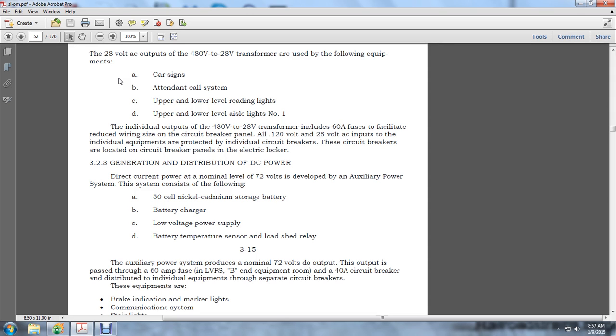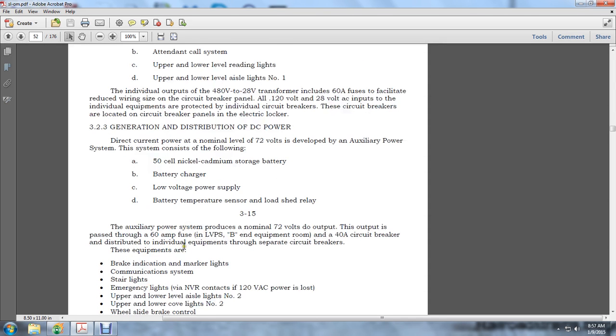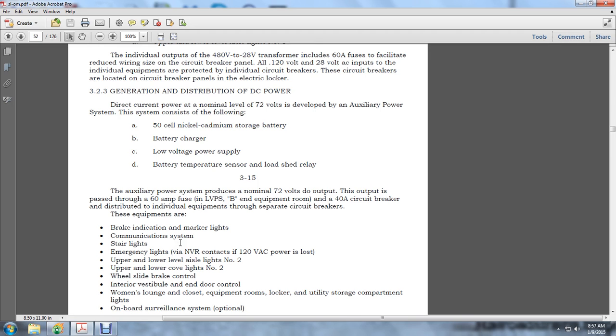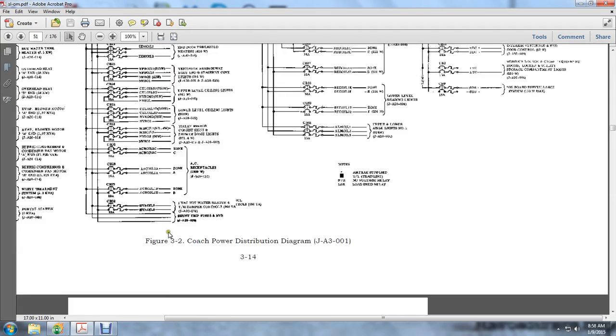3-2-3, the distribution of DC power. The direct current power, nominal 72 volts, is developed by an auxiliary power system. The system consists of the following: a 50 cell nickel cadmium storage battery, a battery charger, low voltage power supply, a battery temperature sensor, and a load shed relay. The auxiliary power system produces a nominal 72 volt DC output. The output is passed through a 60 amp fuse to the LVPS at the B end of the equipment room, and a 40A circuit breaker is distributed to individual equipment through separate circuit breakers. These equipments are the brake indication, marker lights, the communication system, stair lights, and the emergency lights, the no voltage relay.